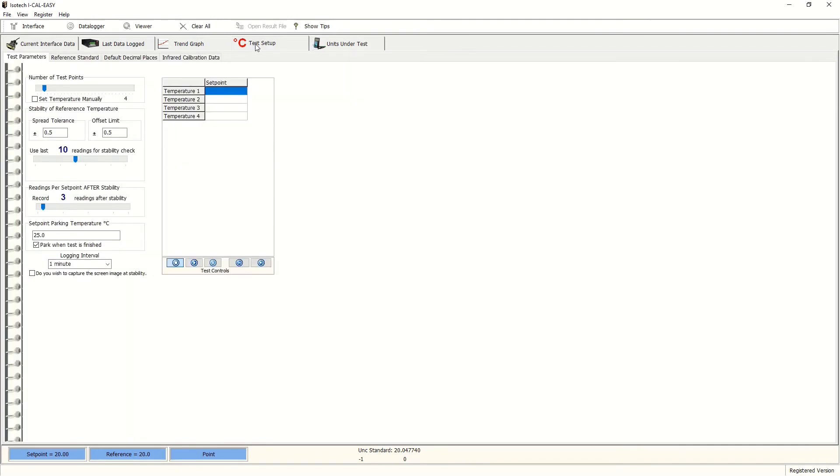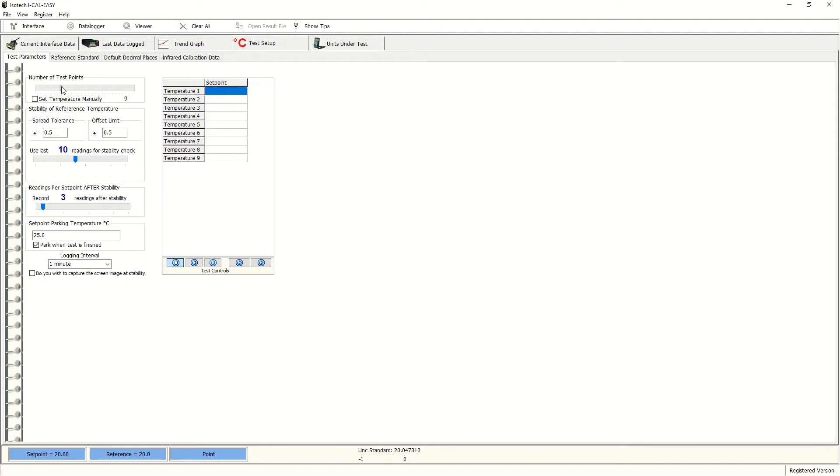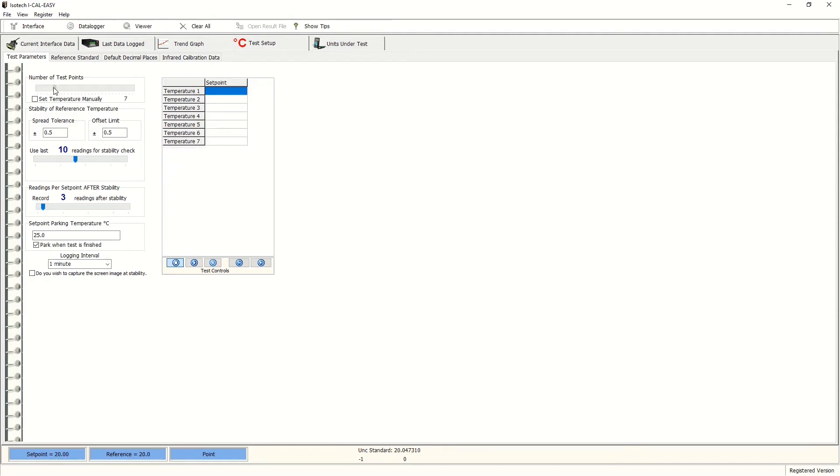So the temperature program. First, you'll see a table here and this can be altered if you want to perform temperature calibrations at many points. You can use this scroll bar here at the top. We'll stick to four temperatures for this demonstration.